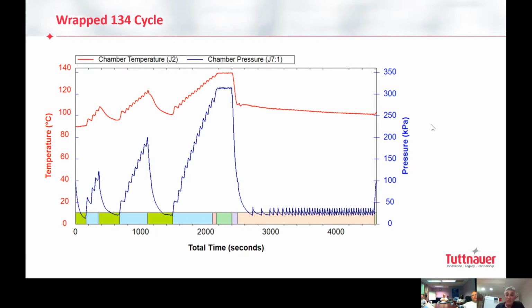So mathematically, we have to prove mathematically, and this is the mathematical proof that we are removing 80%, then another 80%, another 80%. We stayed with 0.8% of the air inside the chamber. It means less than 1%, 0.8. And then we are ready to feed the steam. Once we are feeding the steam, this steam doesn't have to push itself to reach points or places in the chamber or inside the load. It will just get sucked into it because there is a vacuum there. It's there, empty, no air. And this is how we reach this requested or wished penetration of reaching every point.